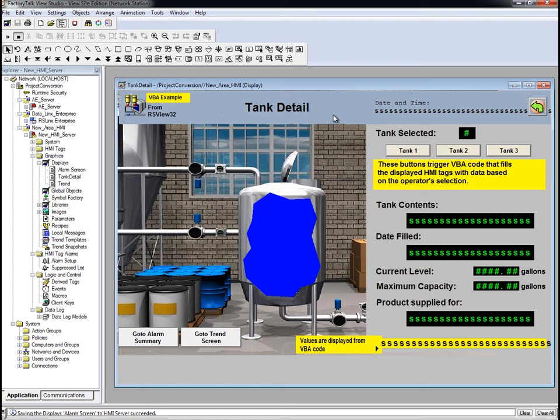RSView32 VBA code executes on the server and does not have exposure to any of the client graphical objects. In FactoryTalk View SE, VBA code executes on the client side of the application and client graphical objects are exposed.